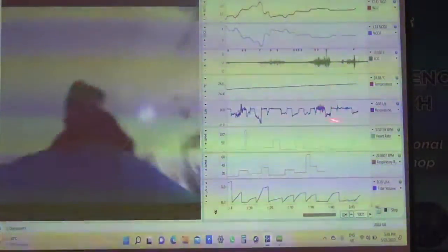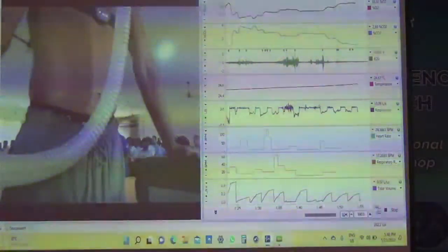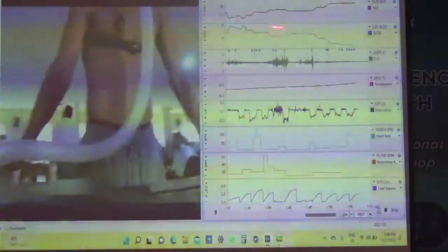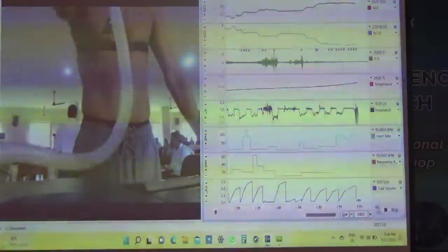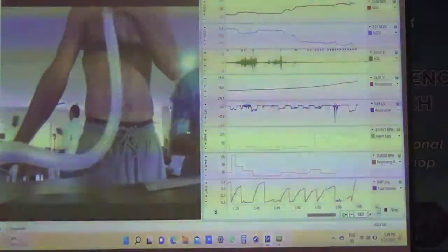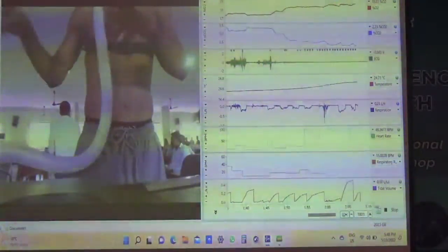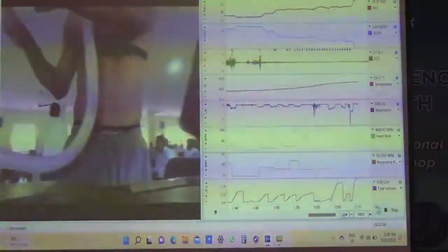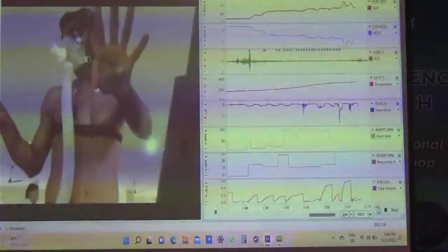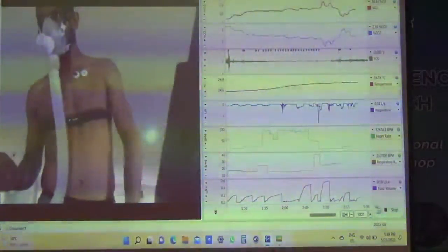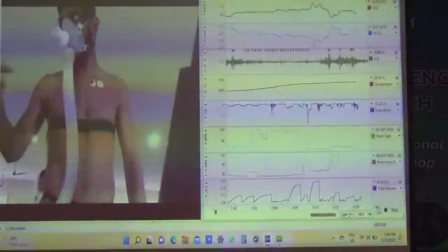And you also have a temperature and a respiration value. And there are some derived parameters like heart rate, respiratory rate, and the time. So these are the raw parameters, and using O2, CO2 and flow, we can derive VO2, VCO2, respiratory exchange ratio, and other parameters. So as the subject starts exercising, we can keep adding comments of different speeds or the variation of the workload so that you can see the graded values of them.